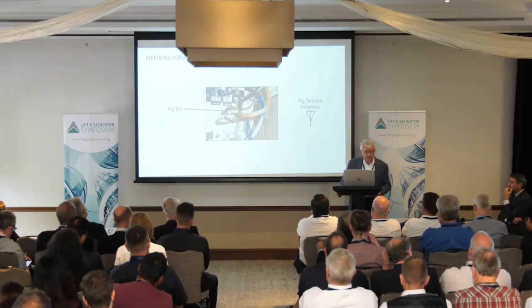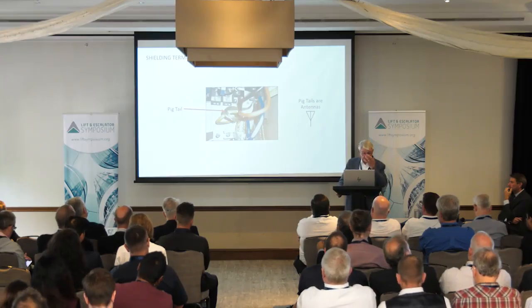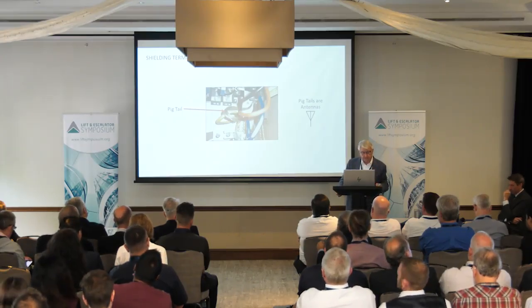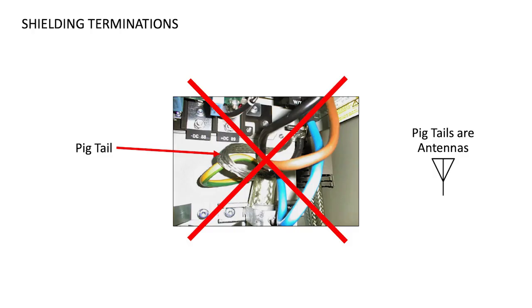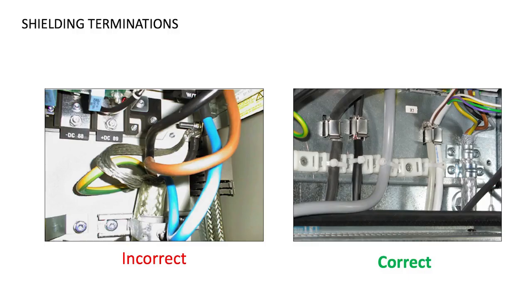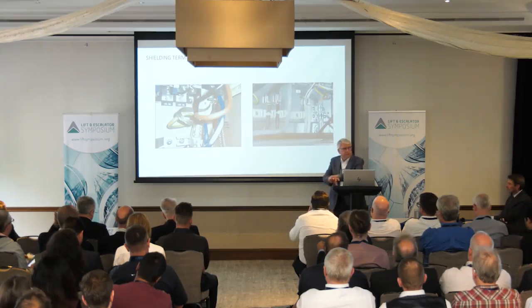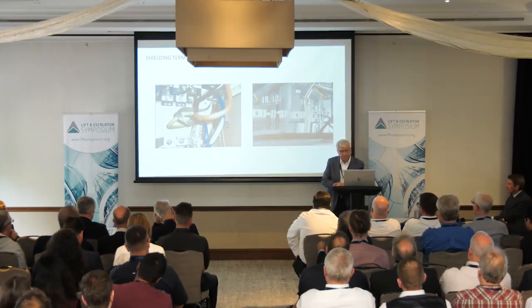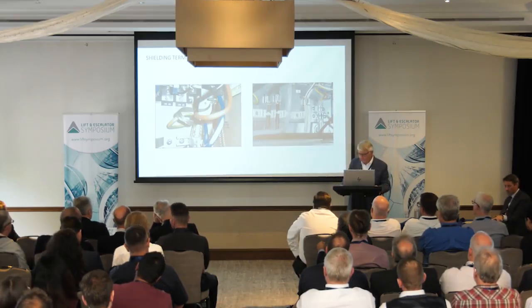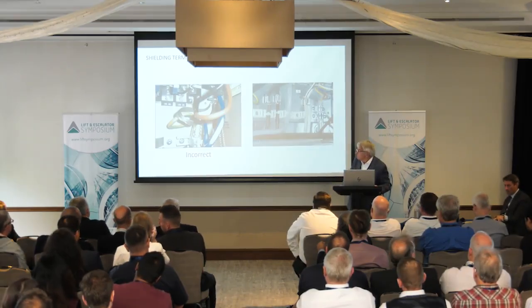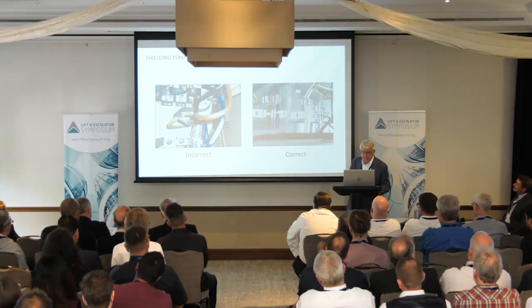So I have some other examples of connections that were not quite done right, but we'll just take a look and compare one more time. Here's the pigtail, and here's how it should be connected. This looks like even a conduit strap, and that's a very common way to strap these down. As long as it grabs the entire shield, it's going to work well. So that's the incorrect, that's the correct.